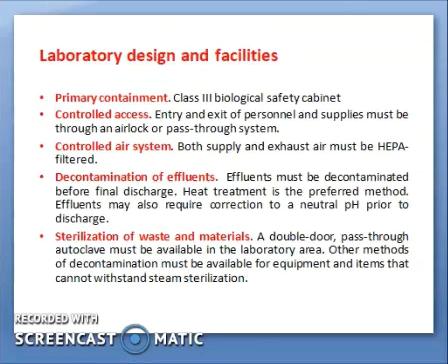A Class 3 biological safety cabinet is mandatory for BSL 4. There should be controlled entry and exit of personnel and supplies in biosafety level 4, and this must be through an airlock or pass-through system.